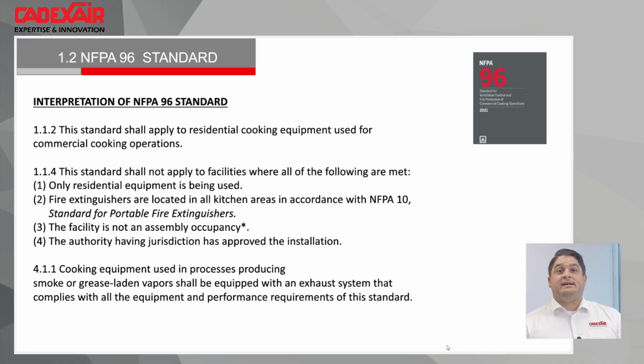Also, the facility is not an assembly occupancy. Okay, we will come back to that later because it's really important, the assembly occupancy. And the authority having jurisdiction needs to approve the installation. And like I already said a few times, it will mainly be the local fire marshal that can tell you, no, you still need to comply with NFPA 96.